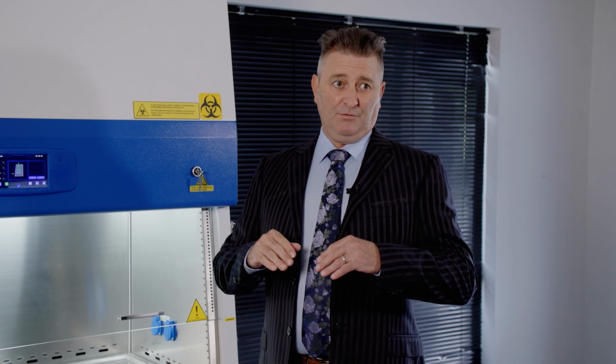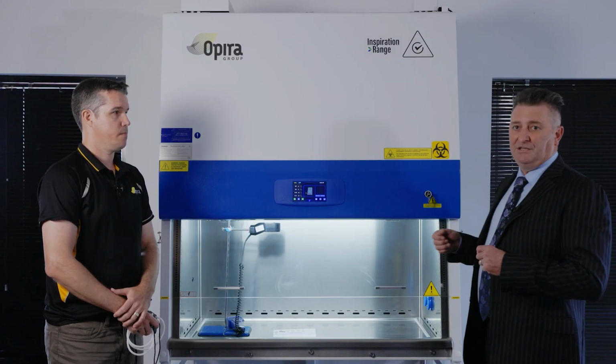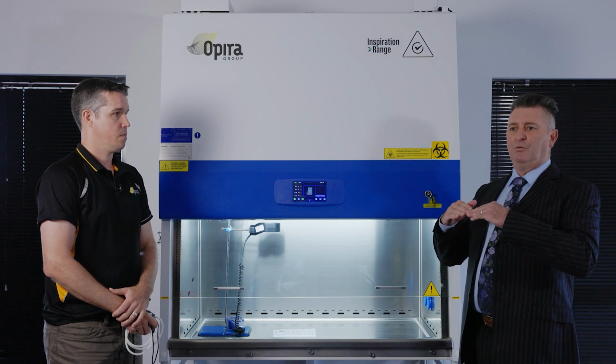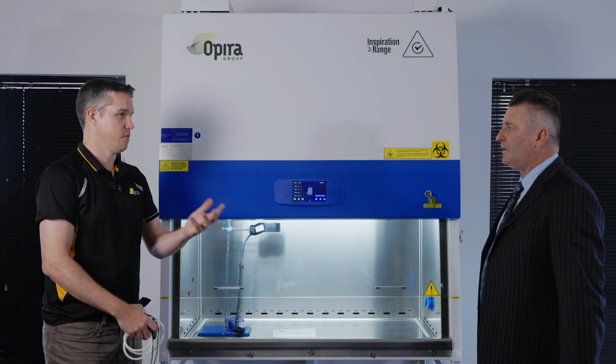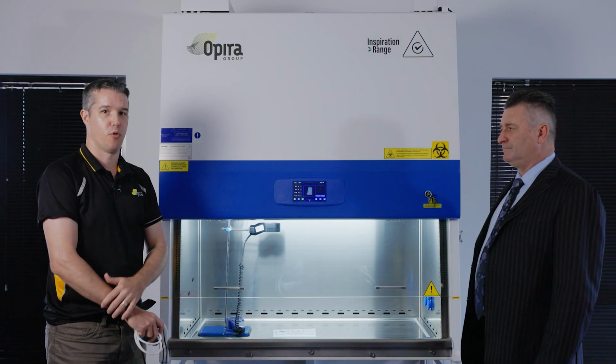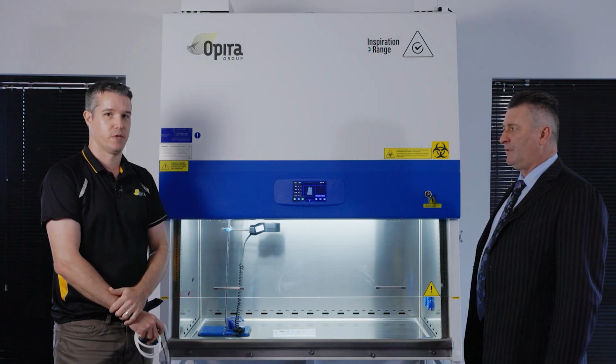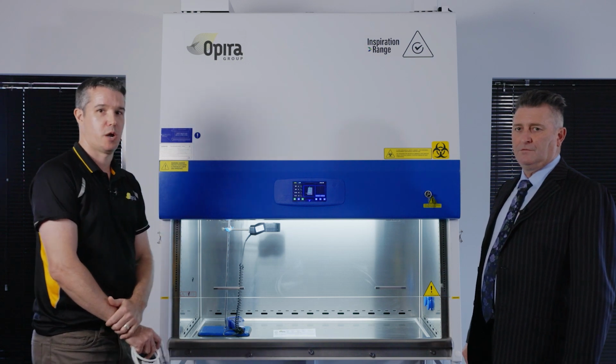Probably the other thing, Curtis, in the standard, some manufacturers might recommend a velocity at a lower level than what's prescribed in the Australian standard. So if that's the case, you would need to report on those performance requirements. Yeah, the standard has that provision, you're correct, and you must report that as a manufacturer requirement if it's a deviation from the Australian test method.